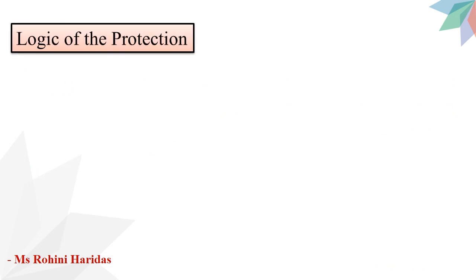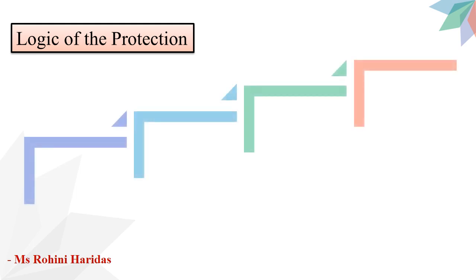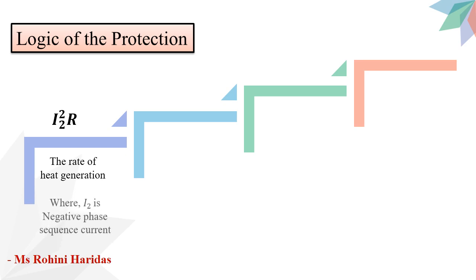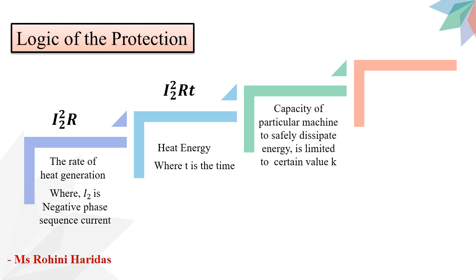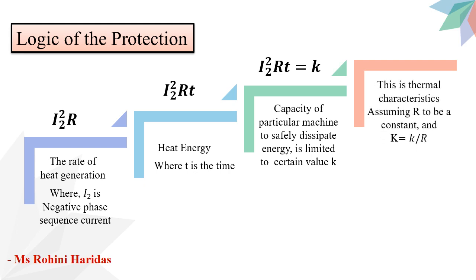Now let us discuss the logic of protection against unbalanced loading. We know that the rate of heat generation is proportional to I₂²R, where I₂ is the negative phase sequence current. We also know that the heat energy is proportional to I₂²RT, where T is the time. The capacity of a particular machine to safely dissipate the energy is limited to a certain value, let it be small k. Therefore, we can write I₂²RT = k. Assuming R to be a constant and capital K = k/R, we get I₂²T = K.